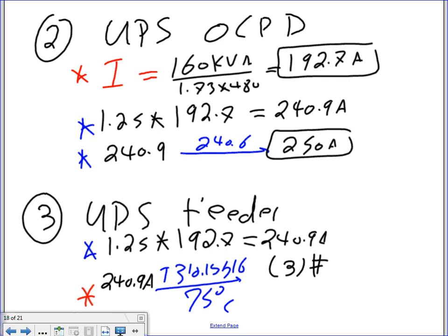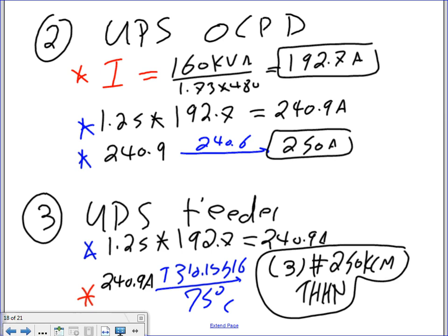Anybody have a second? Gentlemen, ladies, the size of the conductor, 250. 250, and everything is covered, right? 250 kcmil, THHN. So that's the size that you guys are going to have for your project. That's the actual size you're going to have for your project. Cool? Any questions, guys, about sizing the feeder and the overcurrent protection device? Everybody's good with that?